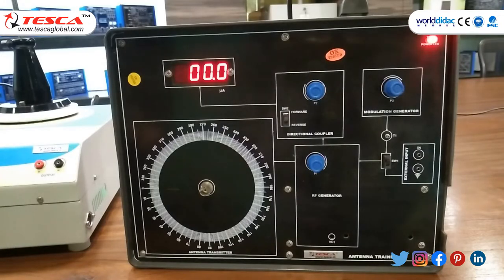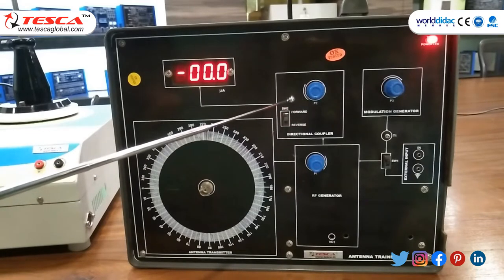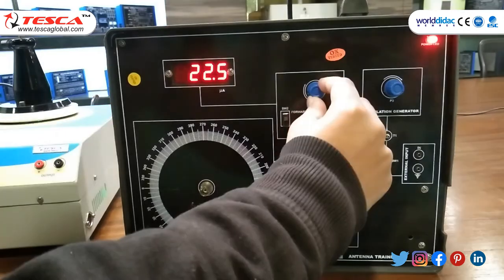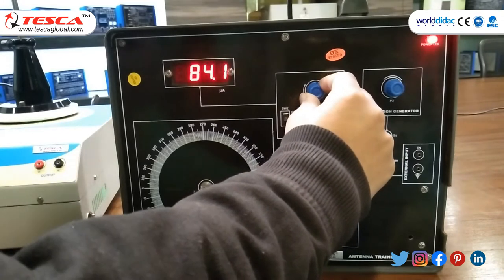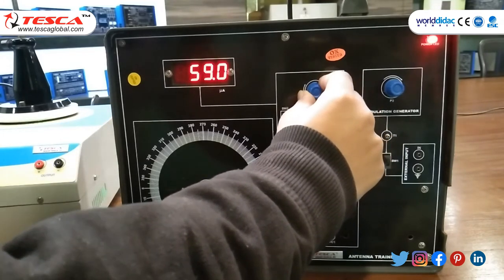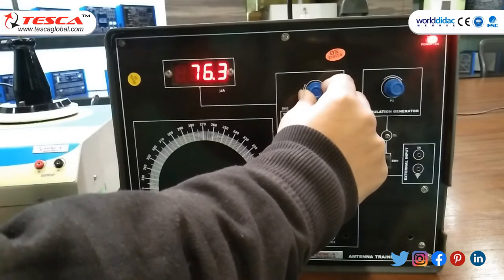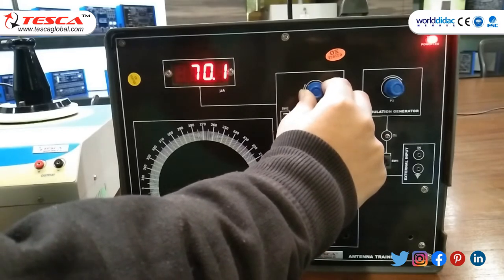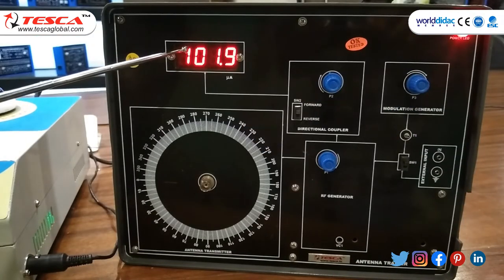The first step of the procedure of this experiment is to vary the FS adjust potentiometer of the directional coupler to make the display reading 100µA. We will vary it until the directional coupler reading goes to 100, which is approximately equal to 100µA.